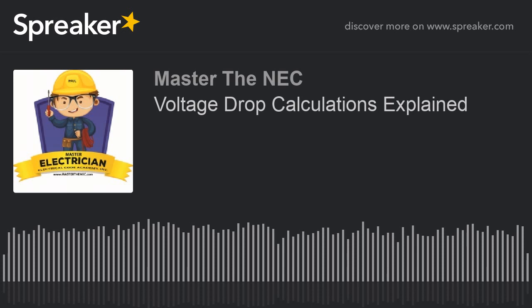So it's circular mils times VD. Now remember, VD, you don't put 3% in there or 5% in there. You're putting the actual voltage being dropped in there. So it's circular mil, in our case, it'd be a 6 gauge. So we said it's 26,240 circular mil times the voltage drop.